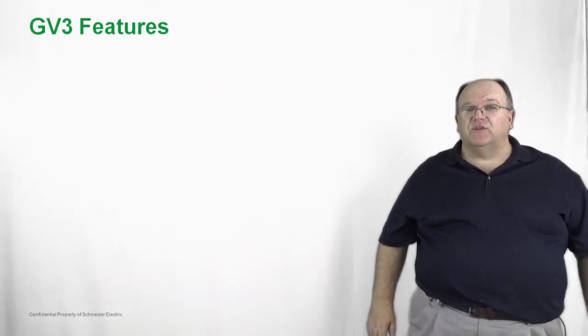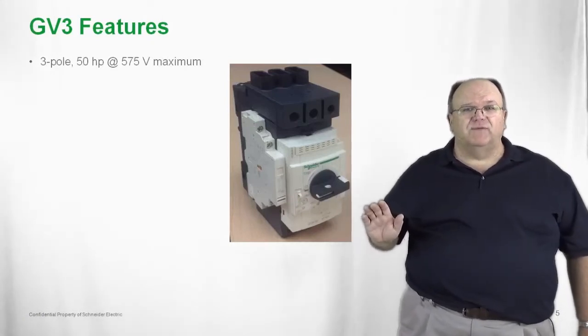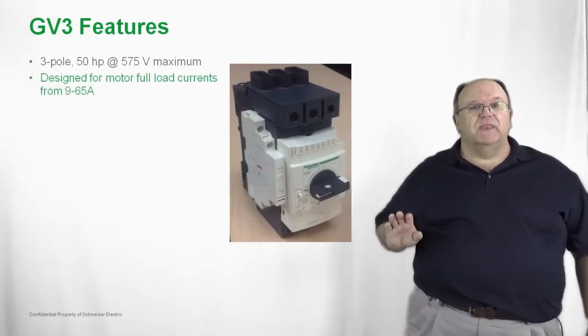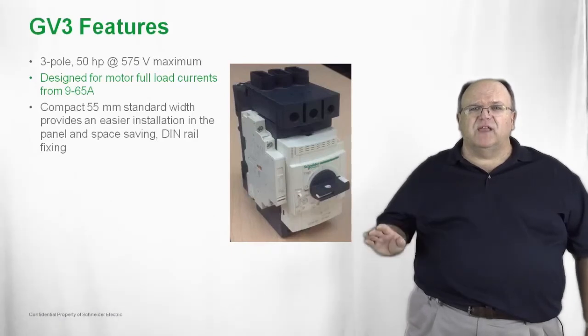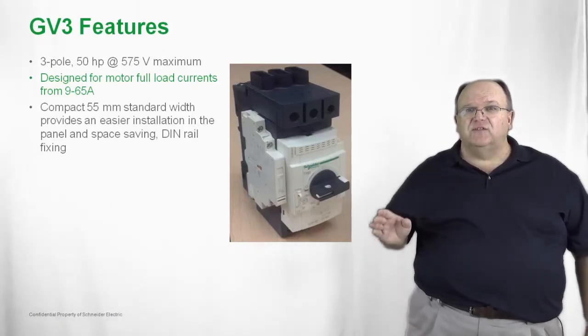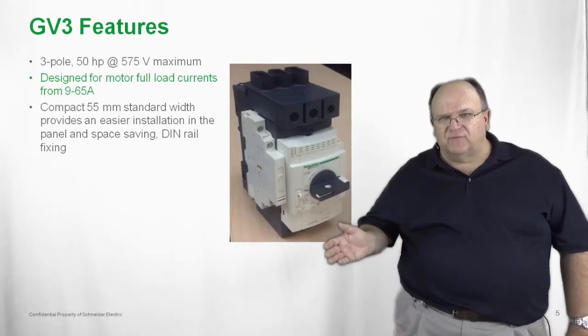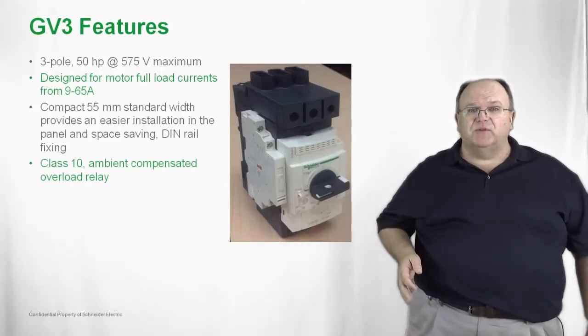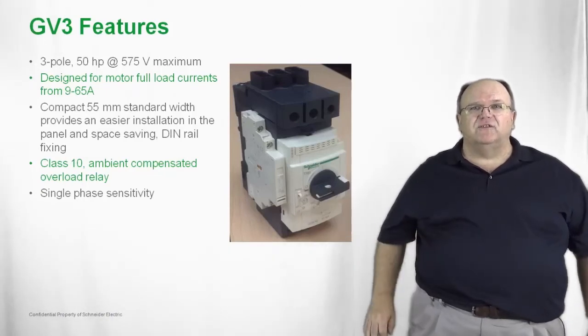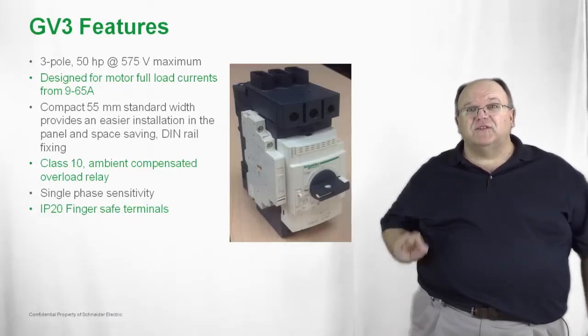The GV3P is a three-pole design covering horsepower ratings up to 50 horsepower at 575 volts, designed for motor applications from 9 amps up to 65 amps, in a 55 millimeter width — the same width dimension as the TeSys D IEC contactors. The contactors and GV3 products mount in the same vertical arrangement, but they can also be mounted side by side if desired. Everything mounts on a DIN rail. The overload relay is a Class 10 ambient compensated overload relay with built-in single phase sensitivity and phase unbalanced protection. It is also finger safe with no exposed current carrying parts, meeting the IP20 standard.